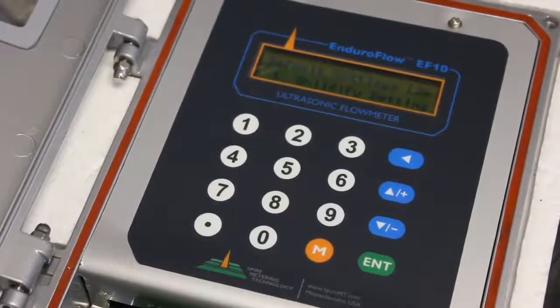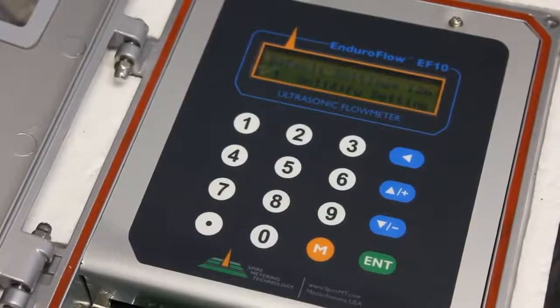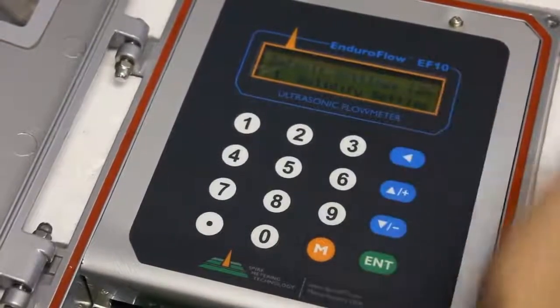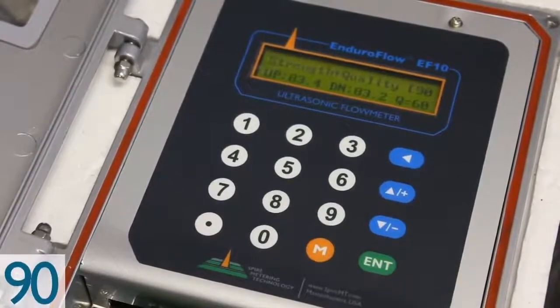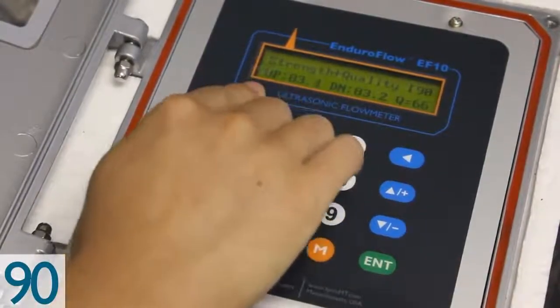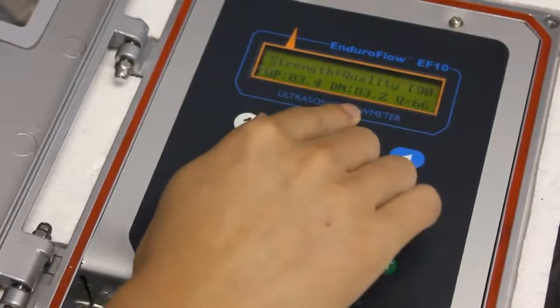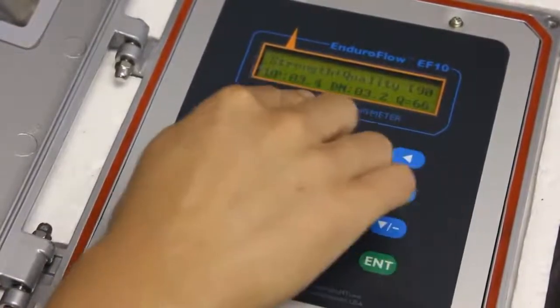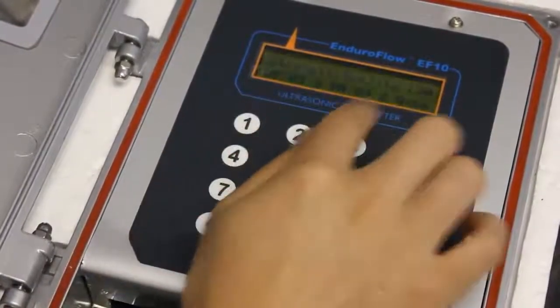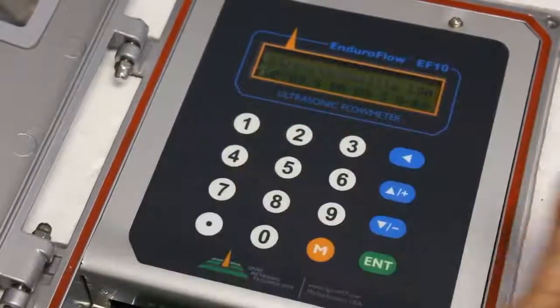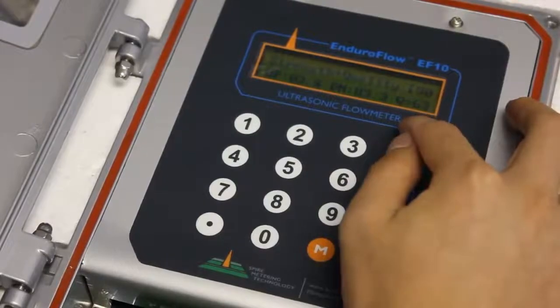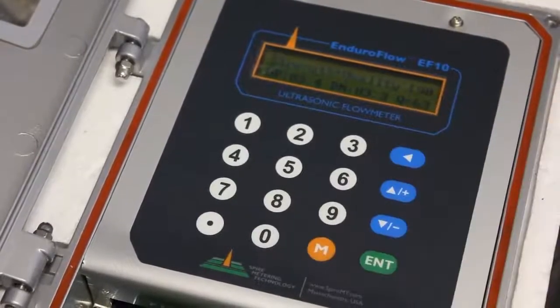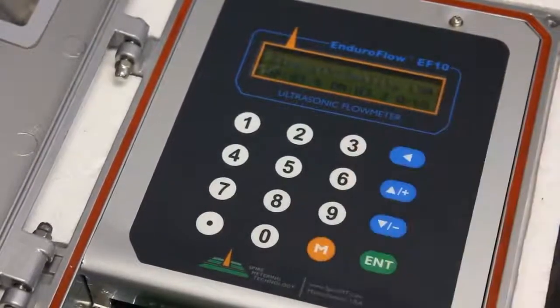To check the strength and quality, we go to menu 90. Now this is the strength for the upstream. This is the strength for the downstream. Both of these values should be between 60 and 99. So as we see they're fine at 80 and 83.